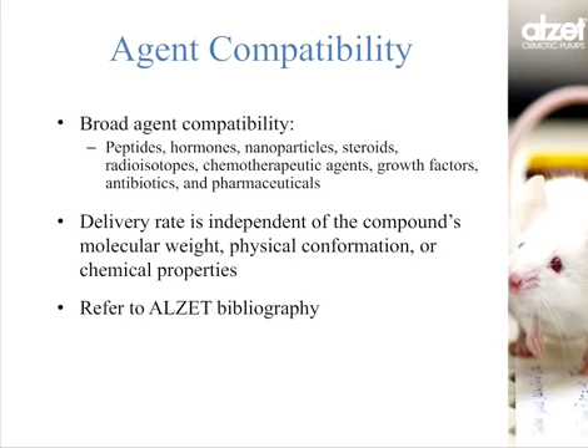Remember that the agent doesn't exit the pump through the semi-permeable membrane. The agent exits the pump through the stainless steel flow moderator, exiting through the tip of the flow moderator, the inner diameter of which is pretty large with respect to any size macromolecule.